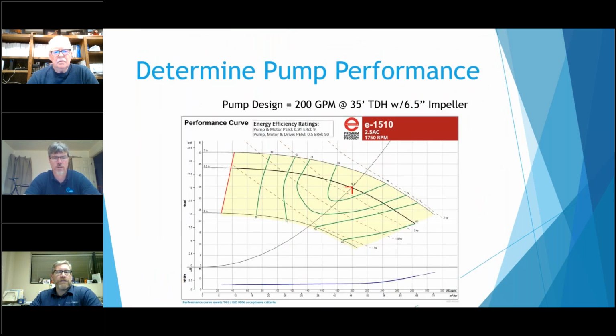So we take our curve for this pump. It was supposed to be 200 and 35, so we're not getting to 30 feet. We actually have, we're not getting to 35. We actually have a little bit less. So we're going to plot the 30 right there on our pump curve and go down. And we see we're doing about 230 GPM or so. The way to get that back is to close that triple duty valve or balance valve. So we draw that back and add pressure so we get back to the point where we want to operate.